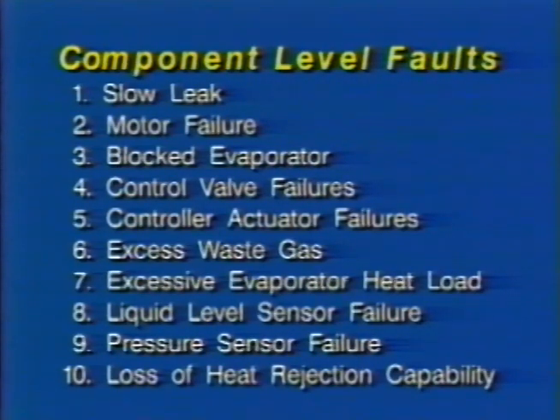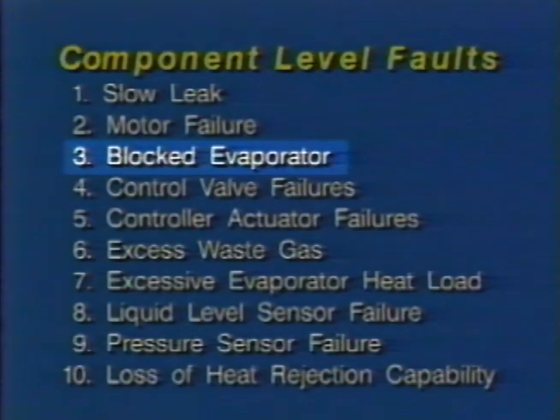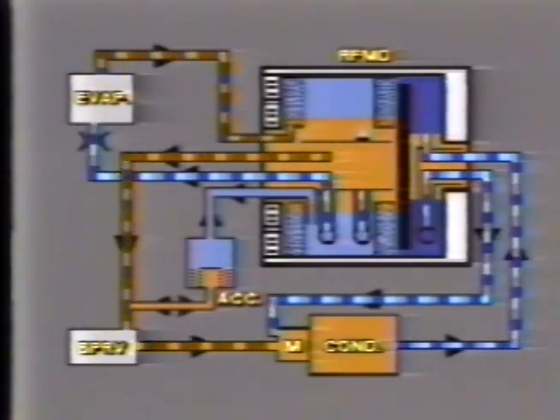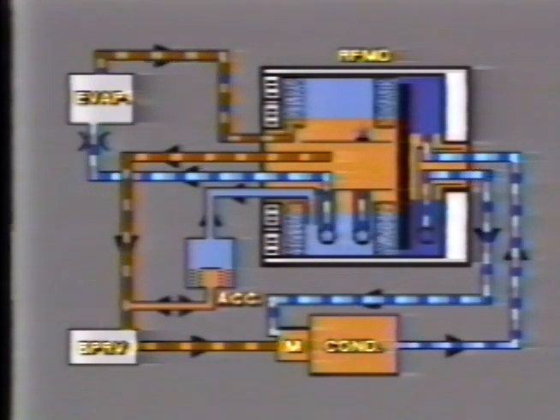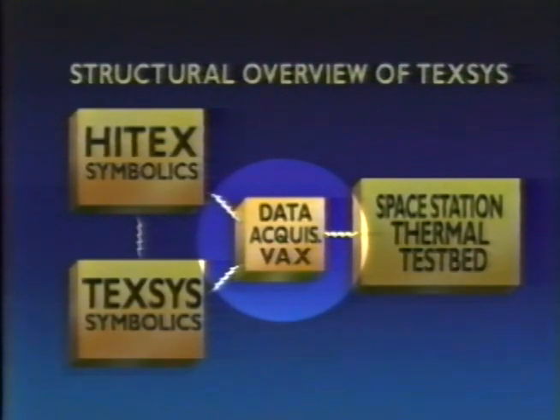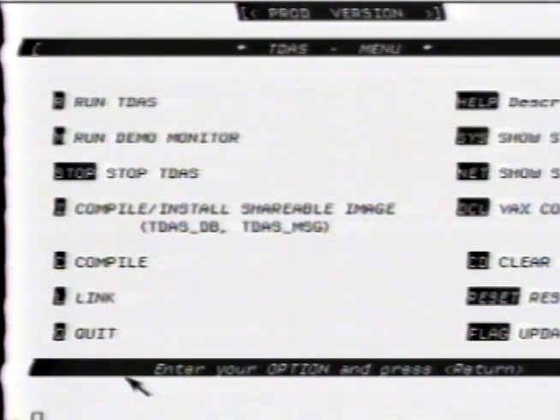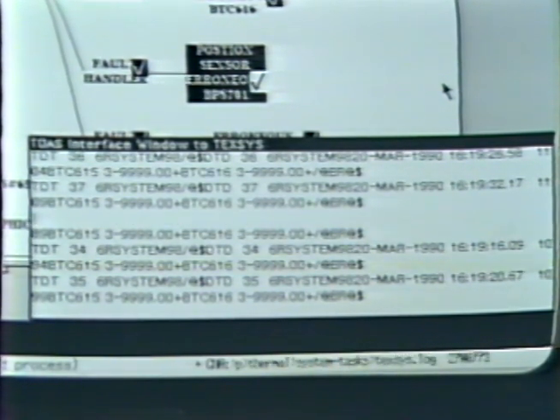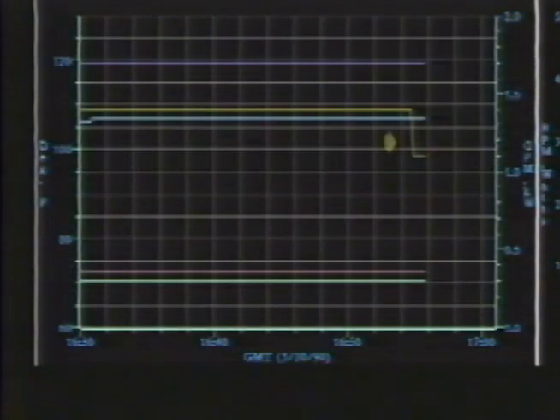As an example, we will examine a blocked heat exchanger fault. If trash or a valve failure prevent fluid from reaching the evaporator, it will go dry and overheat. The TEXSYS Data Acquisition System, TDAS, receives raw sensor data from the hardware, calculates trends, and compares values against allowable range limits. TDAS only sends values which violate predetermined limits, instead of flooding TEXSYS with static sensor values at each update. The partial loss of flow due to the blockage has been observed. However, temperature trends are not yet increasing.